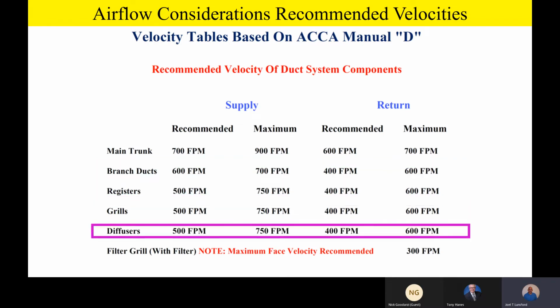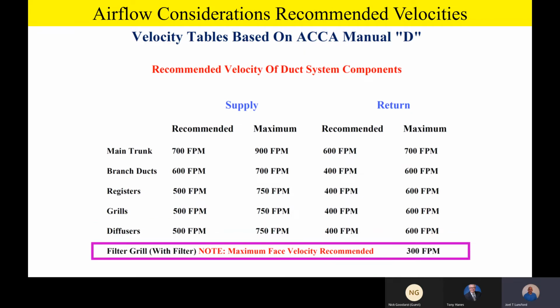Registers and grills are all about the same: 500 feet a minute recommended on supply, 400 feet a minute recommended on return on grills and registers and diffusers. But this is a really big one, especially down in Florida and Mobile, Alabama, where I live, along the Gulf Coast. It seems like there are a lot of homes that have a single big return or maybe two returns with filters in the return grill. So if you have a filter in the return grill, make sure that we design that return grill to be large enough to provide a maximum recommended velocity of 300 feet a minute across that filter grill. So if you've got a filter grill with a filter in it, we don't want to exceed about 300 feet a minute velocity across that filter. That's right out of Manual D.